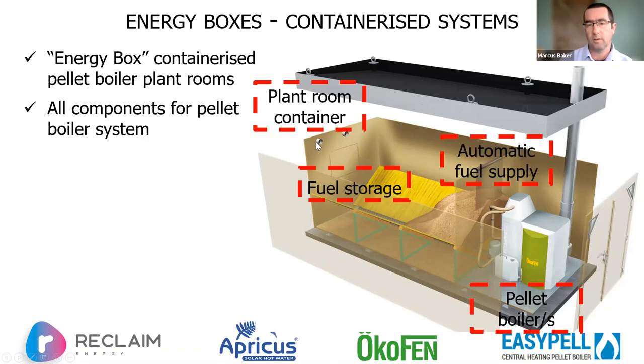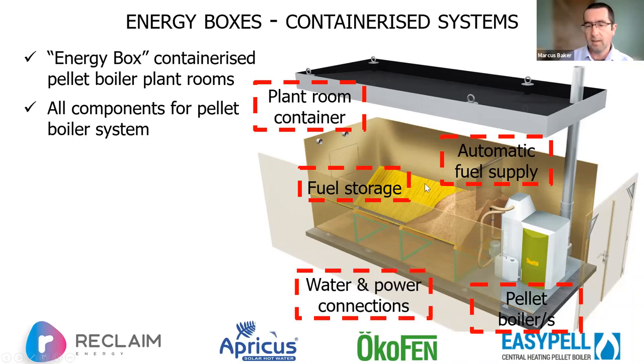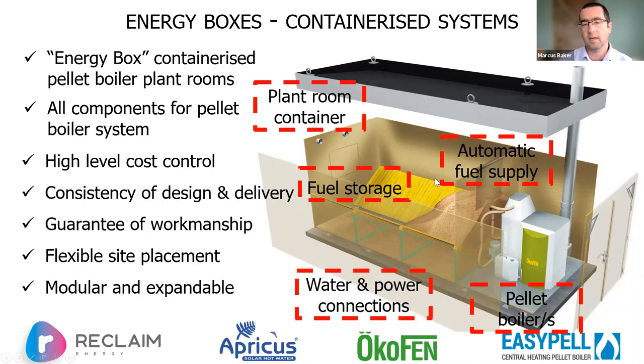And you've got delivery points here. So the pellets will be blown in. There's a little mat here, which deflects them and stops them smashing themselves to pieces and eroding the wall behind them. Equally, delivery could come straight through from the entrance here. We can port it however we want. And then it's simply a case of providing service connections to the container. And you get a really high level of cost control because we can tell you exactly how much the whole plant room is going to cost. And then it's just a case of putting a pad down, running the flue up, and providing service connections.